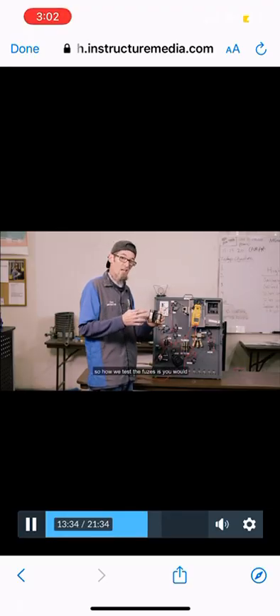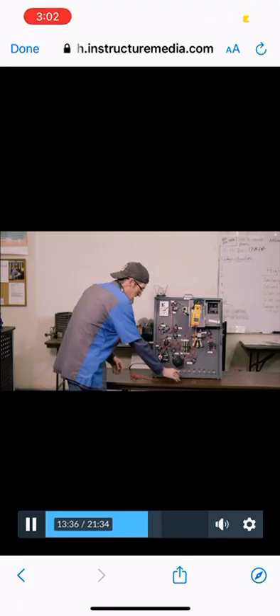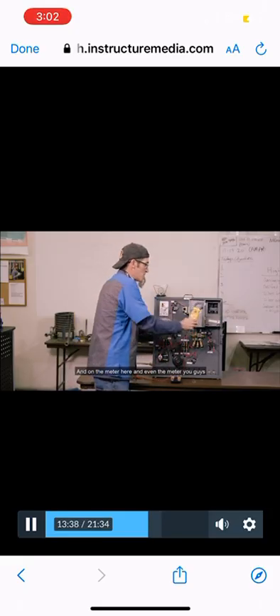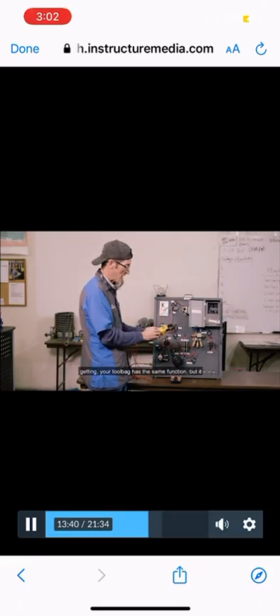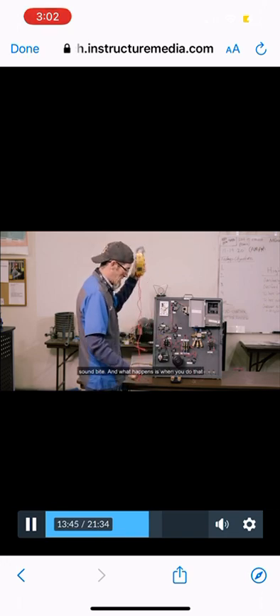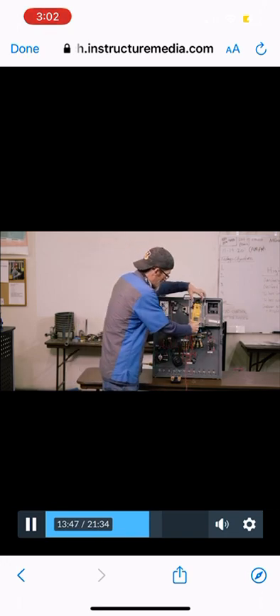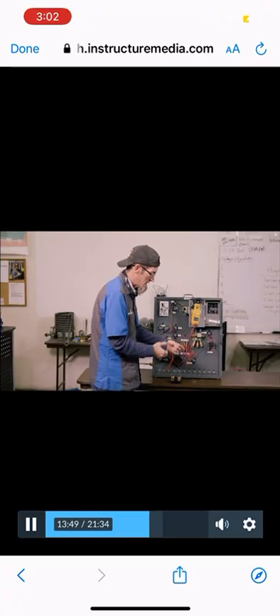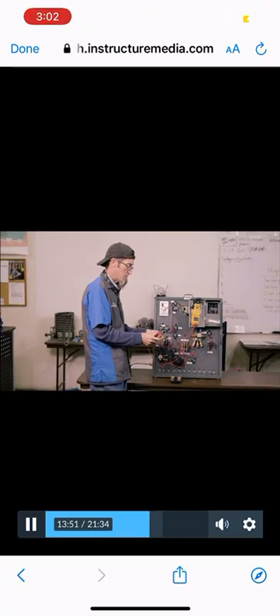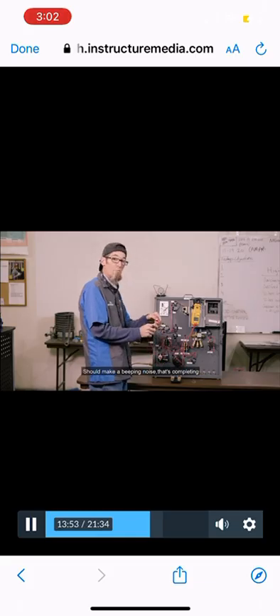Okay, so how we test the fuses is you would take your meter, and on the meter here, and even the meter you guys get in your tool bag has the same function, but it looks like a little sound wave, almost like a little sound bite. And what happens is when you do that, and you take your 2 meter leads and put them together, it should make a beeping noise. Okay, that's completing the circuit.